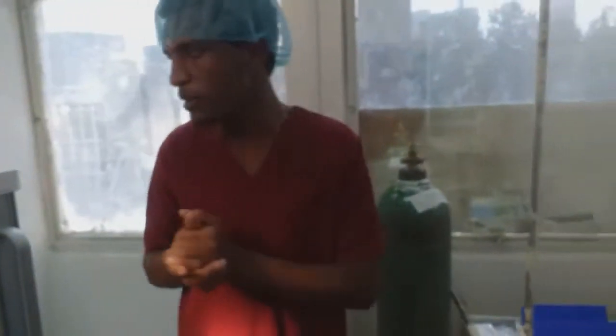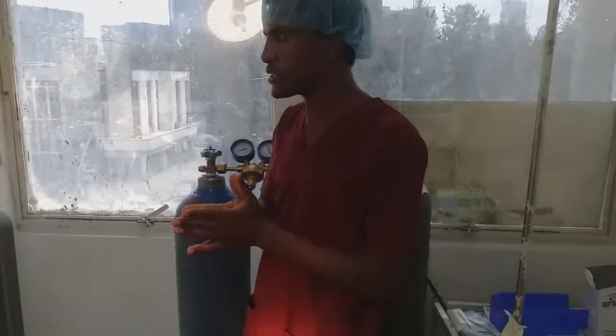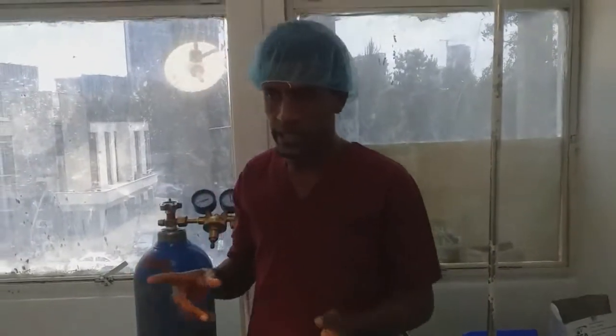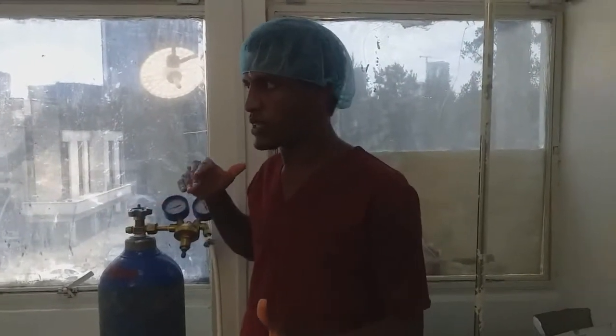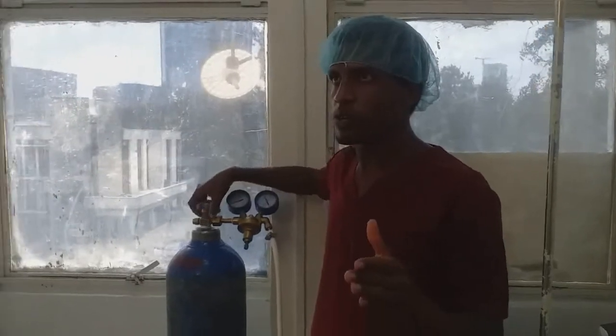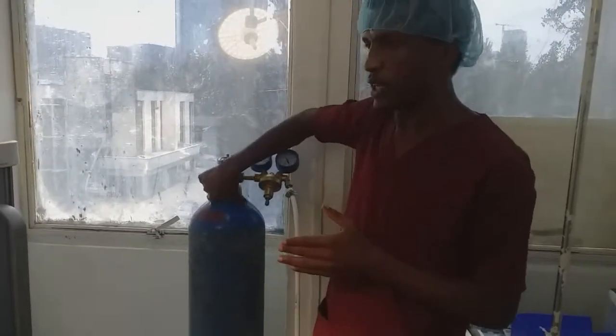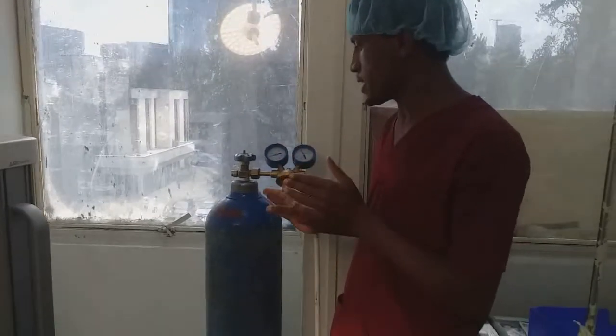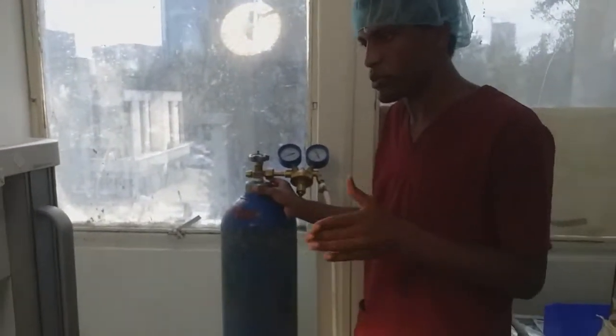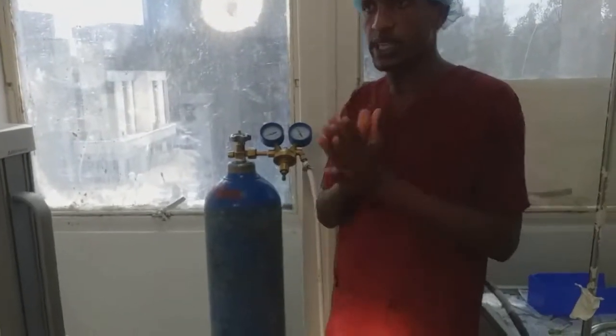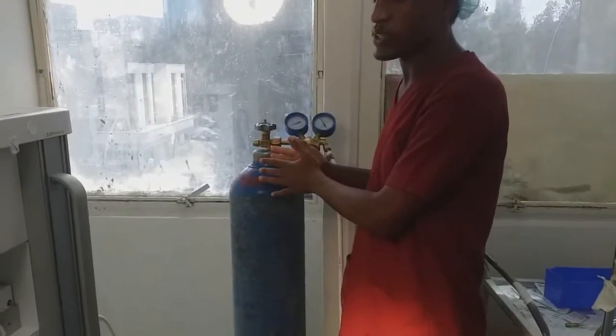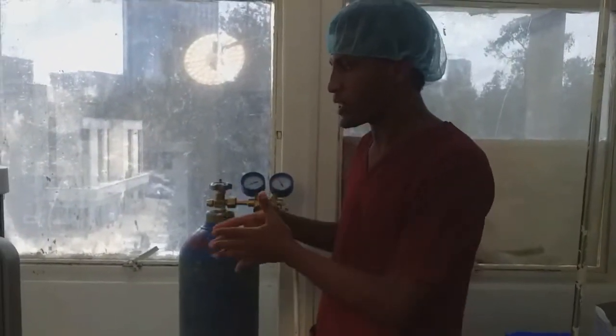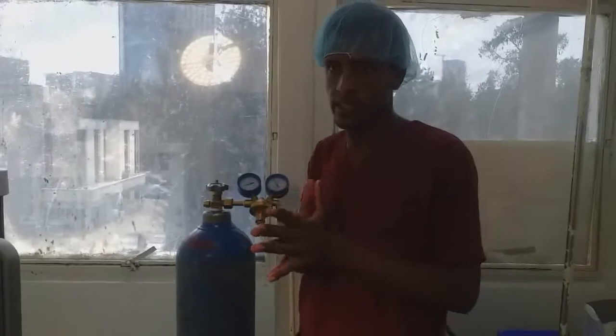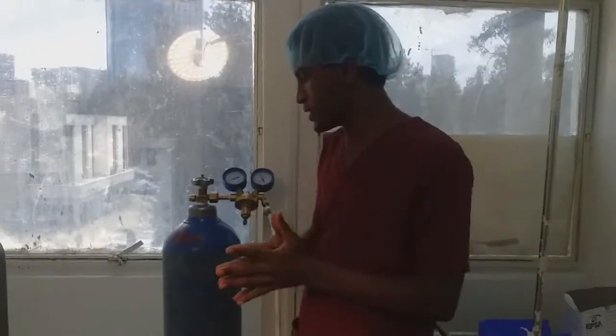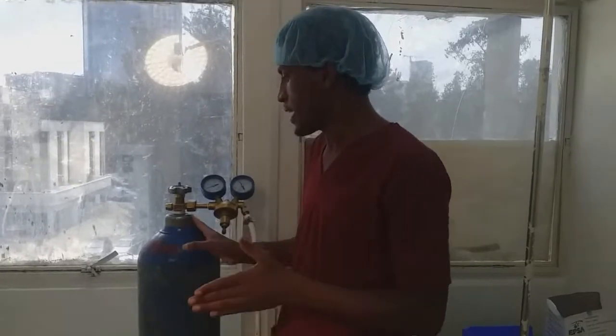The pneumatic component can be classified into three components. The first one is the high pressure system, the second one is the intermediate pressure system, and the third one is the low pressure system. Now, in the high pressure system, the cylinder is the prominent one. So we need to check the cylinder for its oxygen content as well as the type and color. Mostly cylinders are color coded, labeled, and tagged.